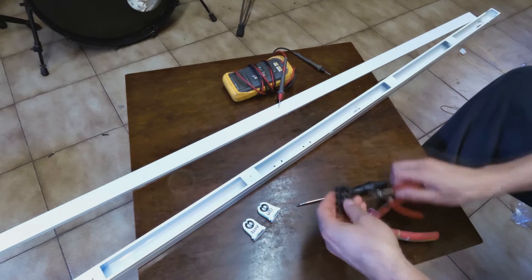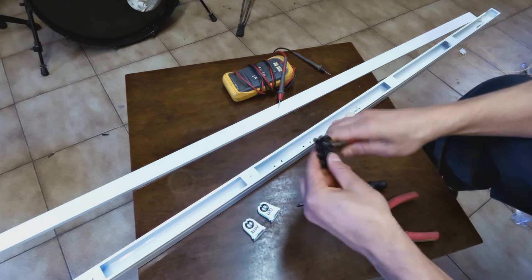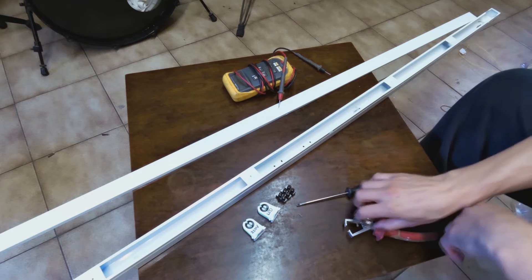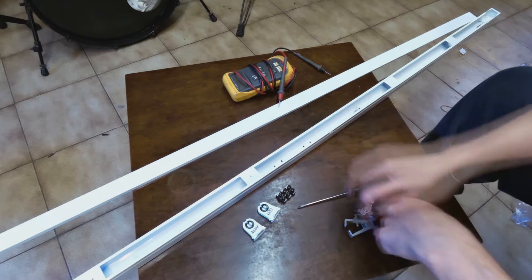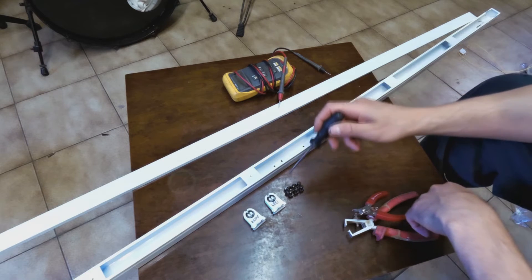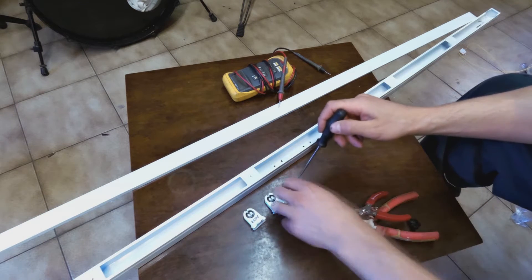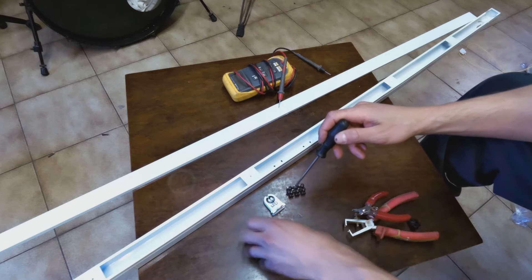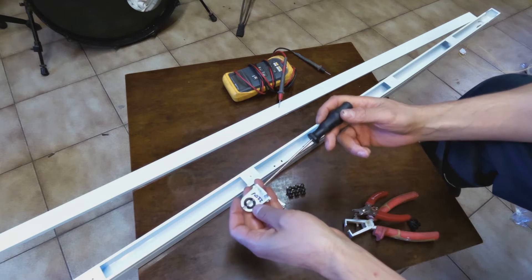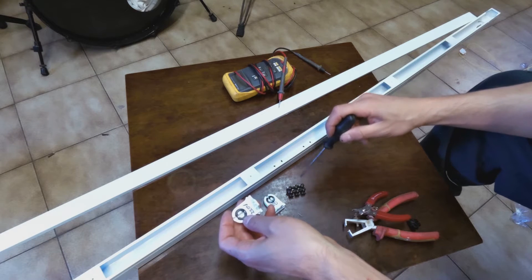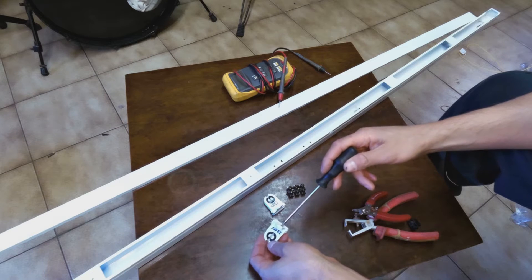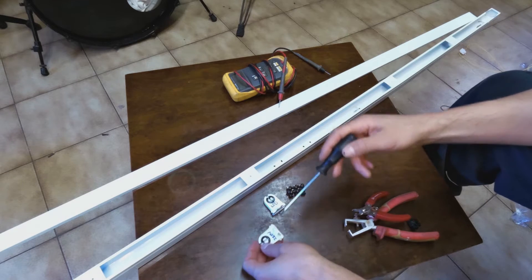So what we in a nutshell need to do is connect these two fittings. You get a terminal block so I'm going to have a three-way terminal block like that and that's connected to the power. So if I had to explain the wiring: the live will go there, out from the live will be wired to one side of the LED fitting. The neutral from the supply will go there and another side will go into the opposite side of the fitting.